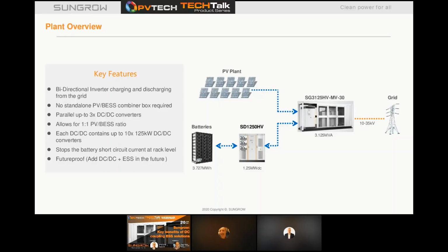To the left of the inverter is the SD1250HV DC-DC converter. This is scalable. You can add up to 3 DC-DC converters per -30 central inverter station. These DC-DC converters work with 1C, 0.5C or 0.25C battery ratings. Another feature to note is that you can install the PV inverter first, and should the business case or the grid requirements change, you can install the DC-DC converters and batteries at a later stage, as the connectivity is already built into the -30 inverter.